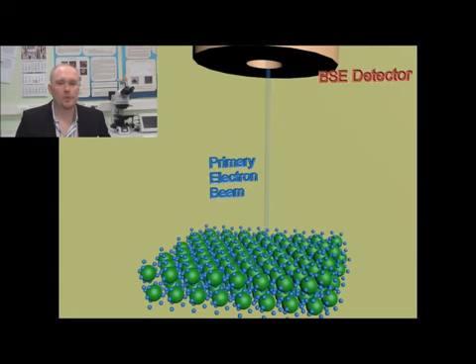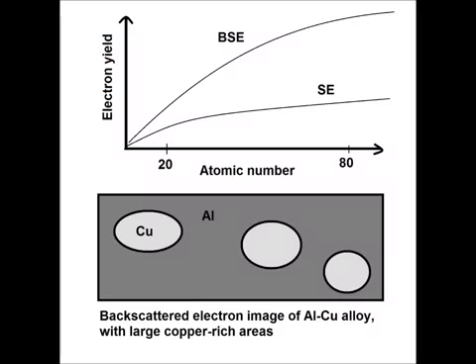Some of the electrons from the primary electron beam interact with the sample in such a way that they don't lose much energy. These electrons will go deeper into the sample and come out in a similar direction. And these electrons, which are backscattered, are then collected with the appropriate detector. The electron yield for backscattered electrons depends greatly on the substrate atomic number. Surface details with a larger atomic number than the surrounding matrix will appear brighter on the backscattered electron image.